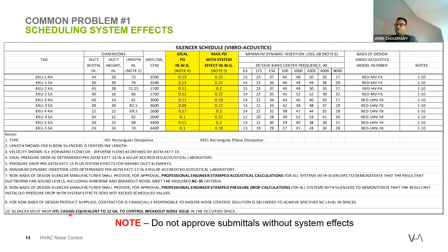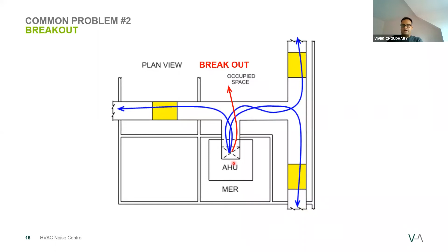So let's take this as an example. If we have this air handling unit located right here, and noise is actually coming through this air handling unit into the occupied space. So somebody looked at it and put these 3-stage silencers, the yellow boxes you're seeing here, to control the breakout noise issue, because they are putting basically a silencer in every single duct. Do you think there will be a noise issue? Yes. And what will that be? Because breakout, basically to define breakout, is the noise which is actually breaking out of the duct itself and going into the occupied space. So this space right here will have a noise issue because there is nothing here to prevent the noise coming from the air handling unit.